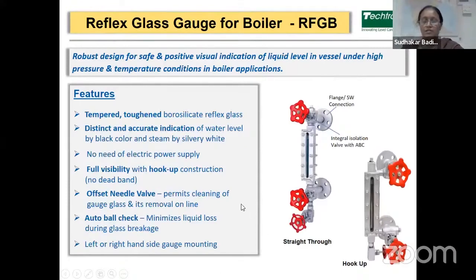So next is a reflex level gauge. This is a robust design for safe and positive visual indication of liquid level in vessels under high pressure and high temperature conditions. The glass used in this gauge is a tempered and toughened borosilicate reflex glass. This reflex glass has 45 degree grooves.